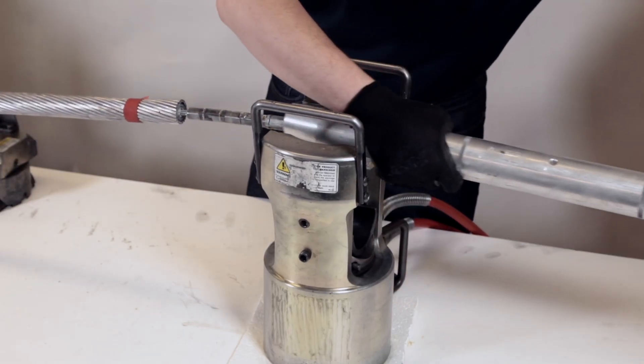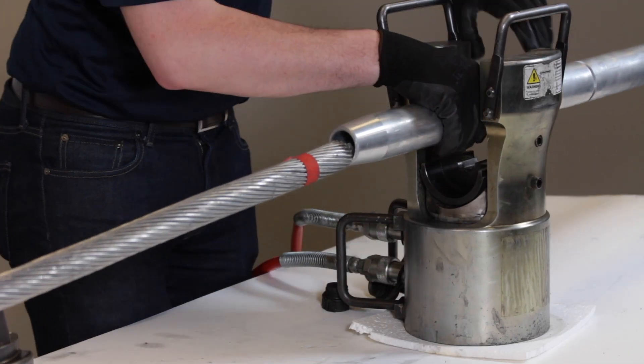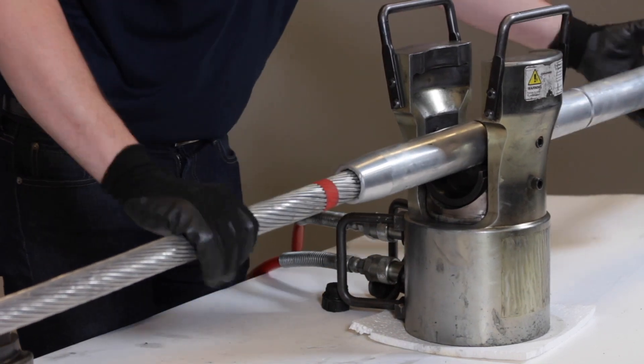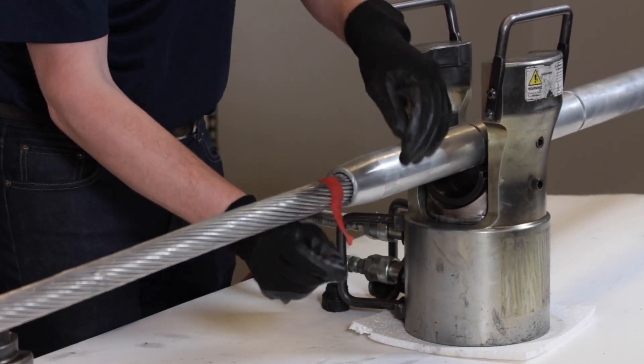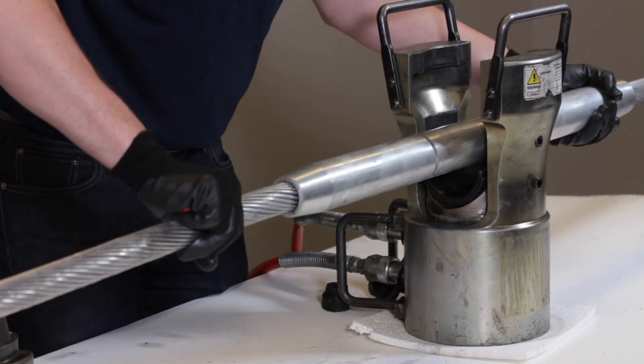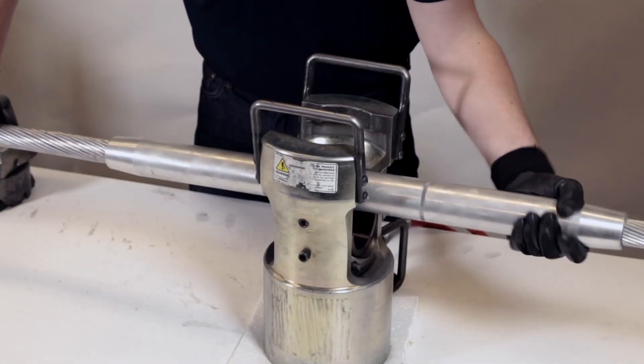Slide the aluminum splice body towards the other conductor until the aluminum strands enter the end. Remove the tape and continue sliding the splice on until the end lines up with the mark made earlier on the conductor strands.